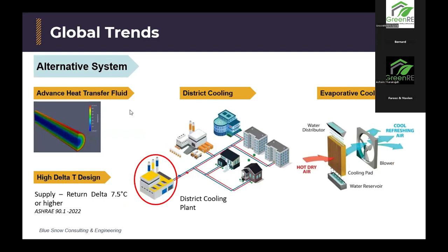Then we have alternative systems. This is mainly on the water side. The use of district cooling plants. We see a lot of use of district cooling plants for townships, especially in the Middle East. It's a very good thing to do because, as building operators, sometimes their main concern is running a mall. They're not going to be very concerned about how to run a cooling plant, and that's why you see sometimes those systems go bad. So by having a district cooling, it's kind of like you purchase chill water at a fixed rate. So it's actually very good because the district cooling plant can be maintained at a much better efficiency if they know how to stage those chillers and part load them well.